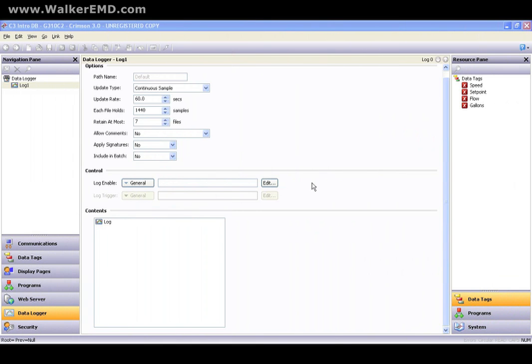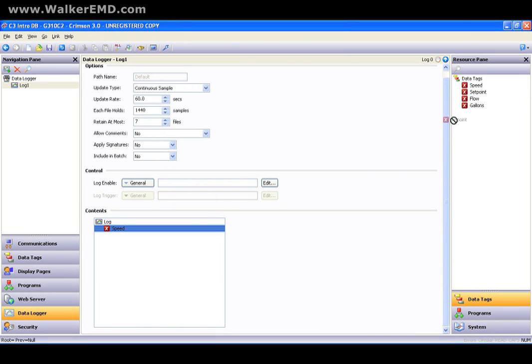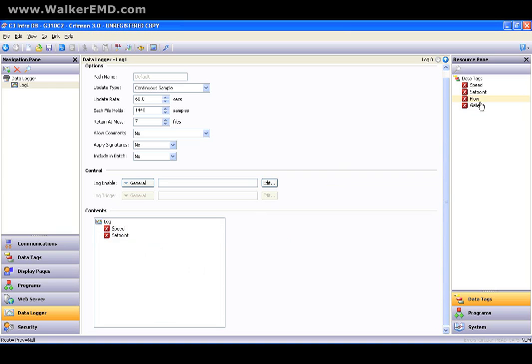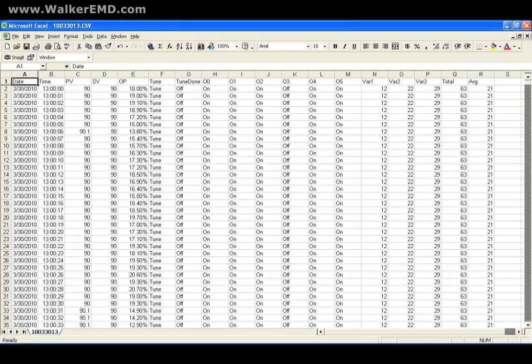What about data logging? After creating a log, simply drag the data to be logged into the contents window — you can multiple-select items for this operation as well. We will log the data at user-programmable rates or on a triggered event. The information is stored in open CSV file format with automatic time and date stamp, and can be accessed through applications like Microsoft Excel.